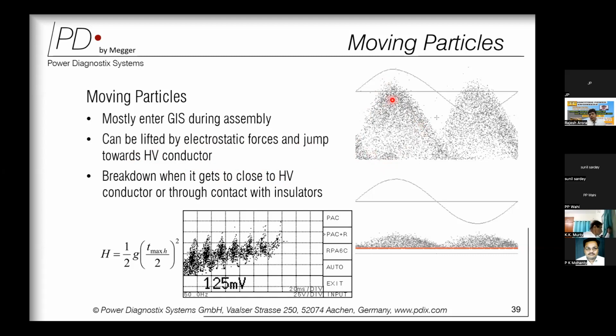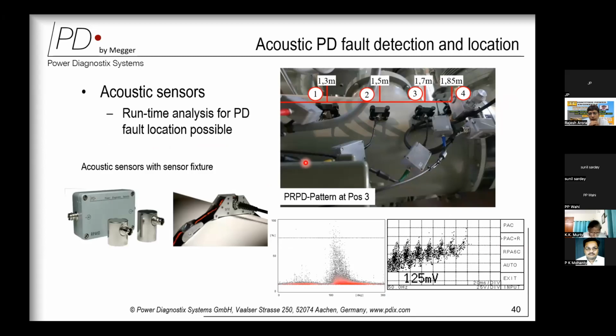So whenever it is a moving particle, as a user we should always measure the bounce time or the length to which the particle is bouncing, so we know exactly whether it is going to touch the HV conductor or not. That is generally done by using acoustic. So whenever we see a moving particle signature, we immediately deploy our acoustic sensor at various positions on the GIS and capture the bouncing particle pattern. Either sensor will give you an amplified pattern, and on that particular pattern this is what we are going to see.